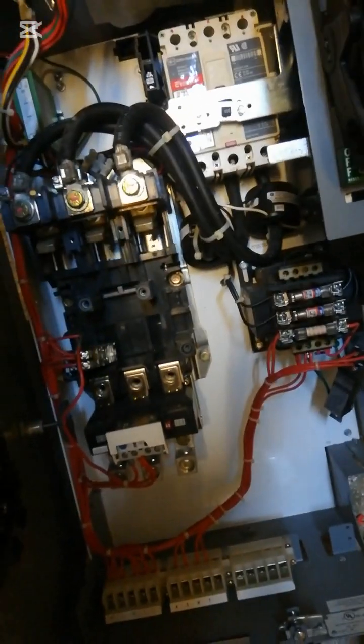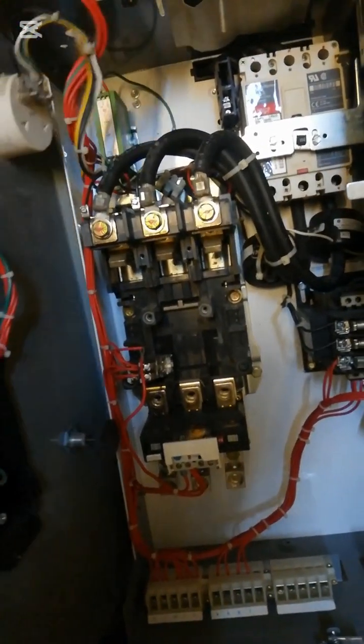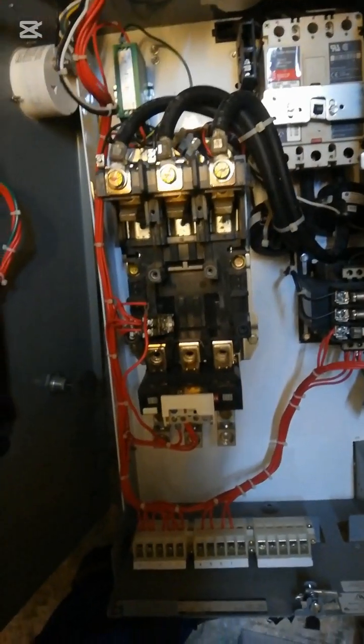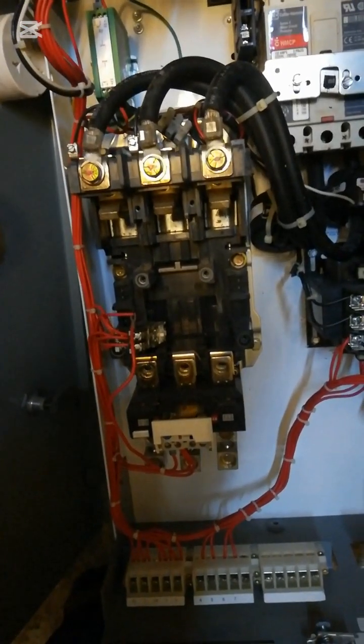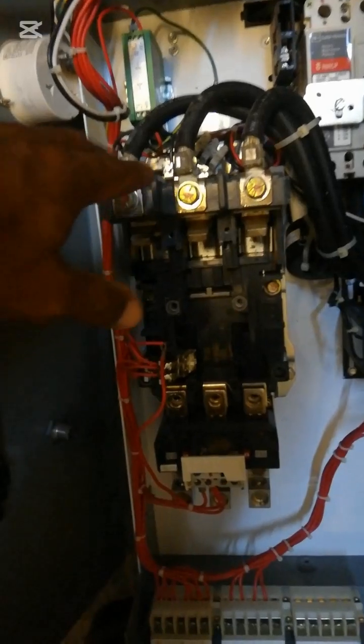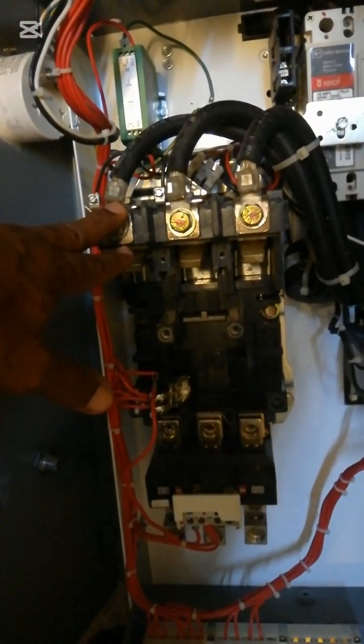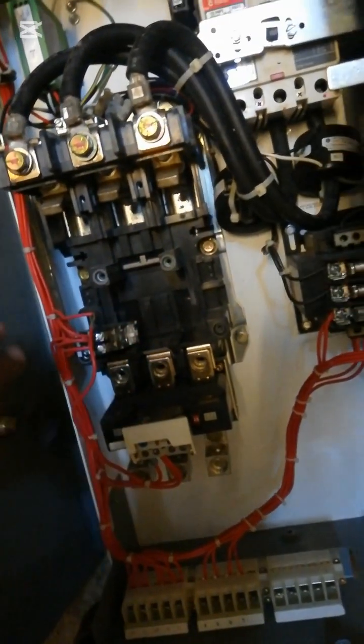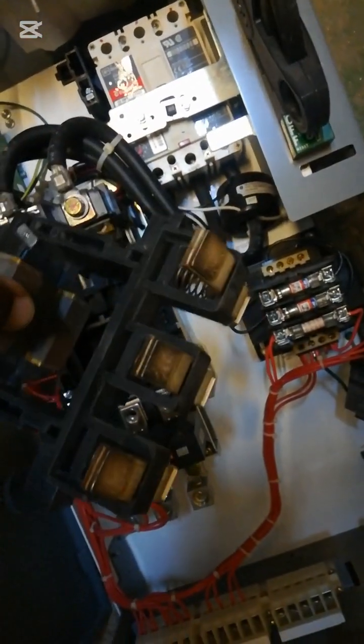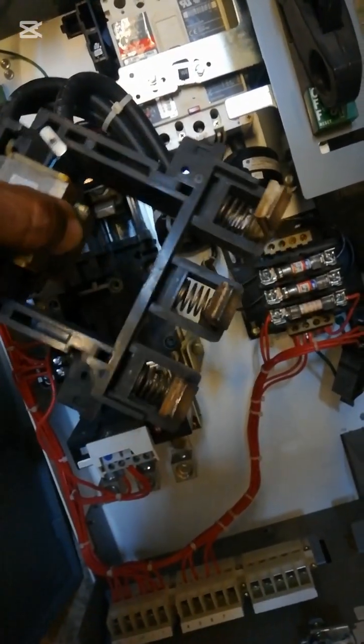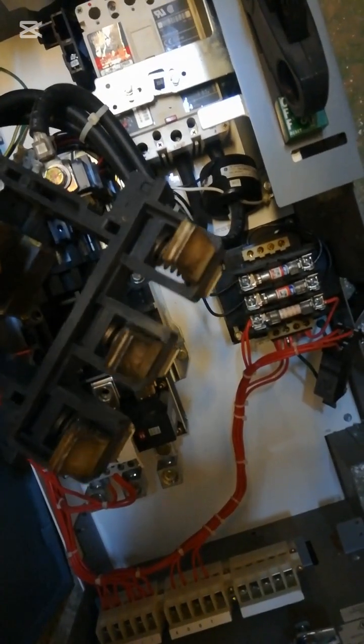Now, opening the panel, you will see the shell for the starter, right, or contactor, right, we use it interchangeably. You have the supply side. In here you will have the coil. You will have the contact point. See that I'm showing you. This is a contactor which has been pulled apart. You have the contact point. These are the contact points.